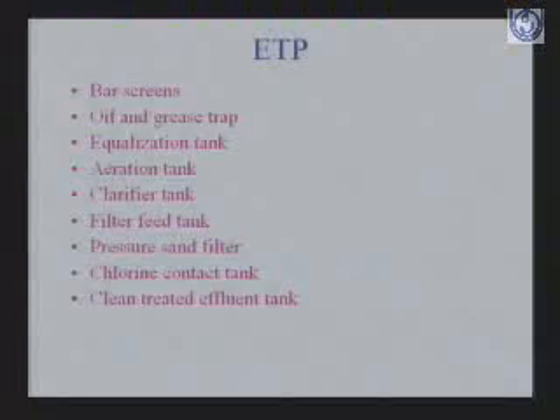This effluent treatment plant consists of the following parts: bar screens, oil and grease trap, an equalization tank, aeration tank, clarifier tank, filter feed tank, chlorine contact tank, and finally the clean treated effluent tank, where the clean water is stored and sent off to different parts of the hospital for maintaining gardens and washing purposes.